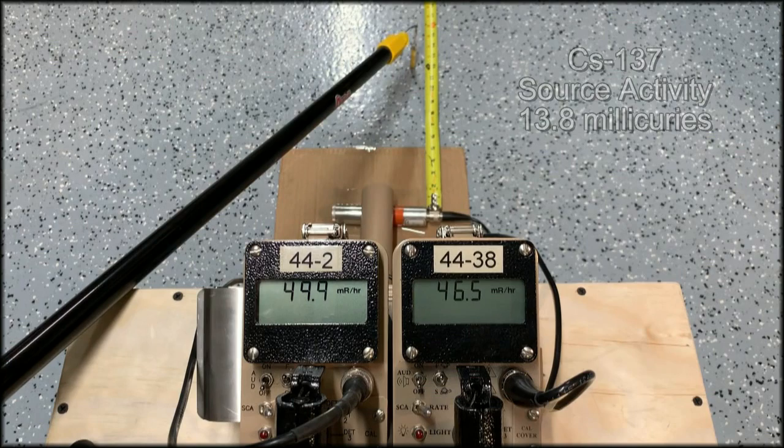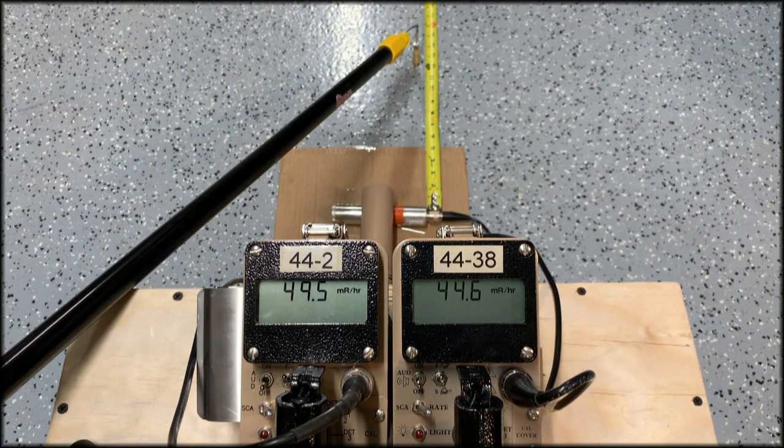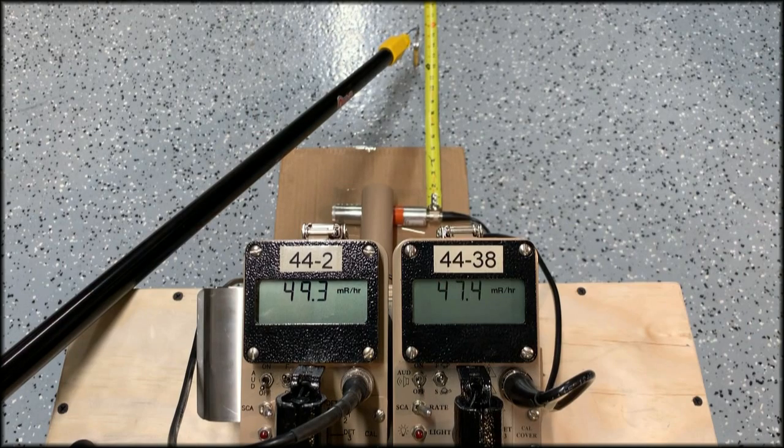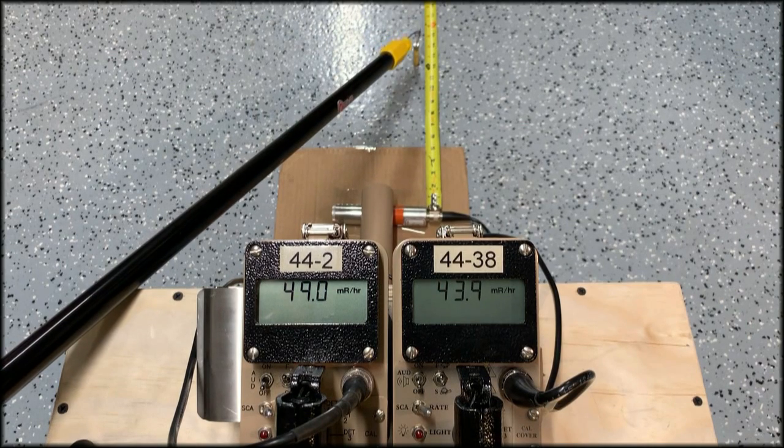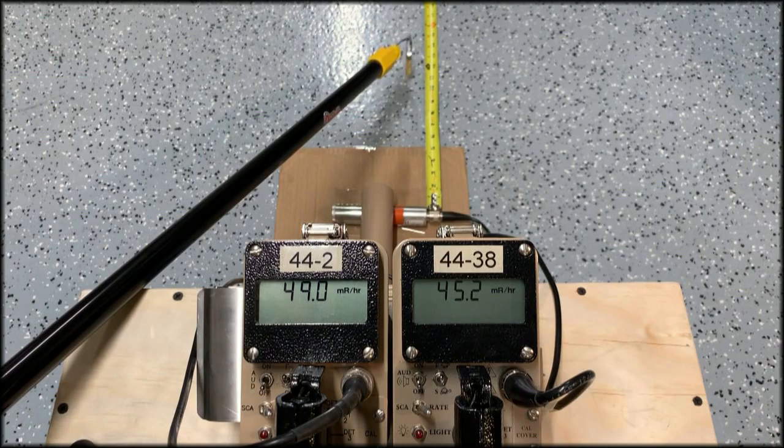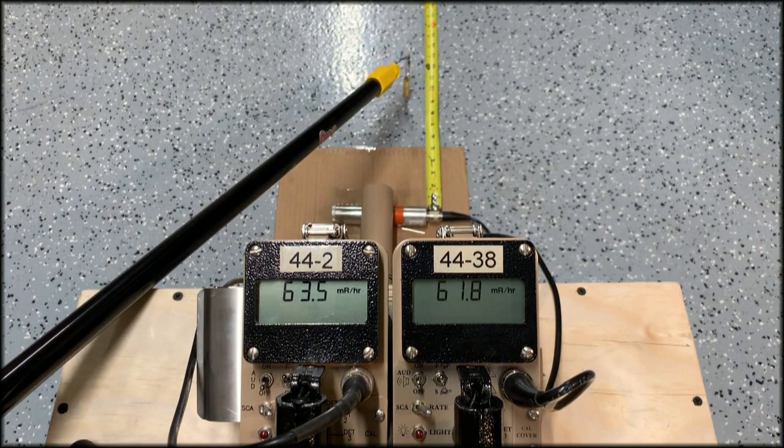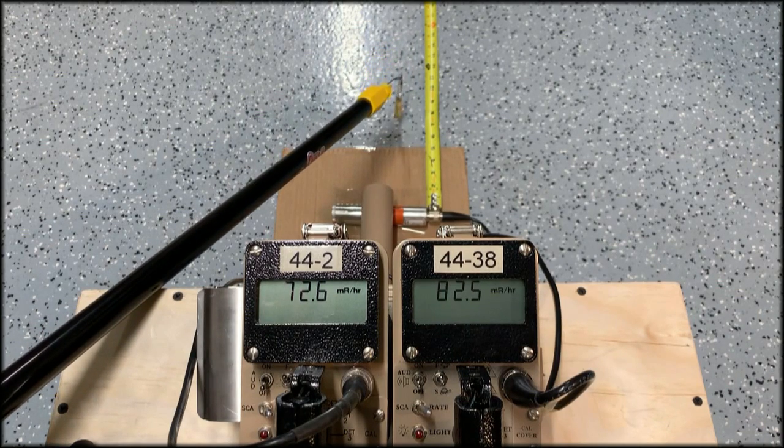And that's where we're going to get to about that 50 mR per hour point. And you'll see that both of these detectors, again, they're both calibrated to cesium. So they're going to read very similar. But as I move in from this point forward, this is where we should start to see the difference in the display of these two detectors.